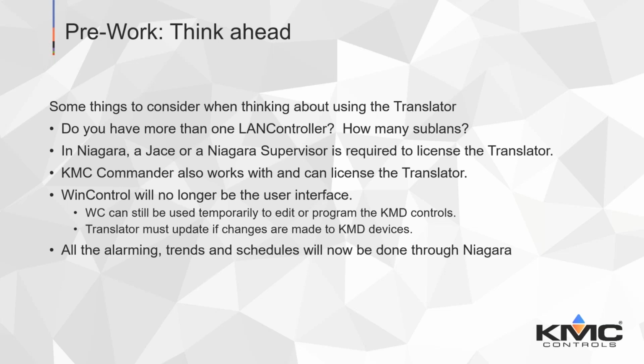So I guess the theory here is if I'm making changes that would change the point definitions, like changing from one data type to another, that's when I want to refresh my translator. Because in BACnet we have a concept of analog and binary, whereas in KMD it's just a variable. If we're making small programming changes, you wouldn't necessarily have to do anything with the translator, but it's something to be cognizant of as you're making changes. What you do has an impact upstream. Correct.